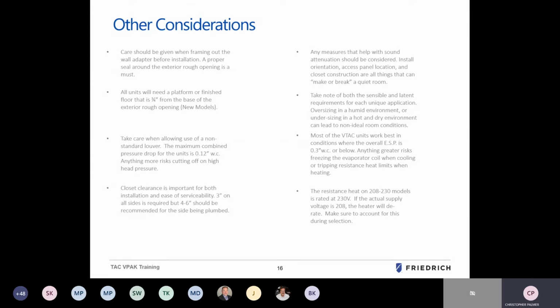The electric heat on the 208/230 models is rated at 230 volts. If you do supply voltage at the 208 mark, you will derate the heat output. So when you're sizing your heater and your units, make sure that you correctly account for the derated value of the electric heater based on the supply voltage. That's a critical measurement that is often overlooked.